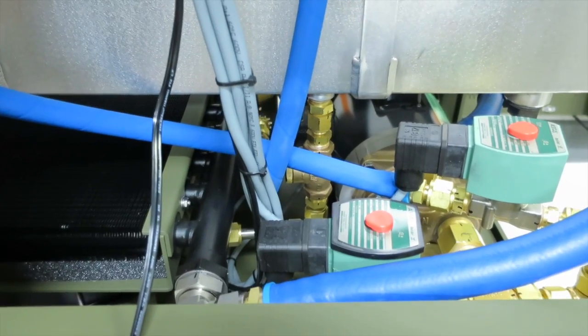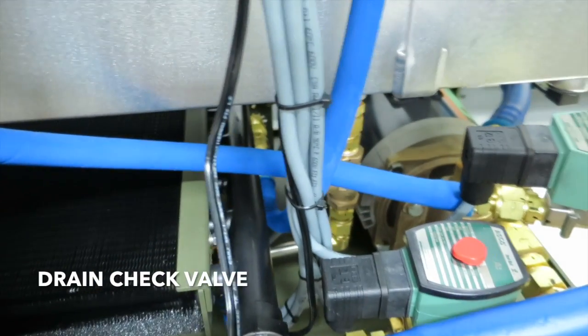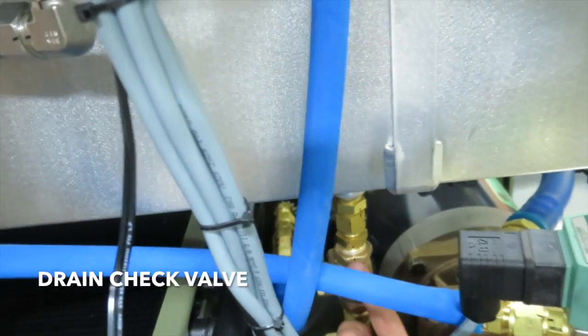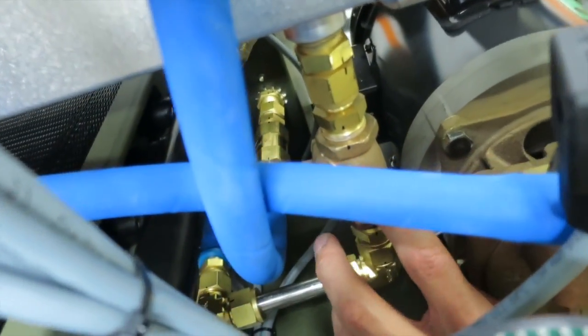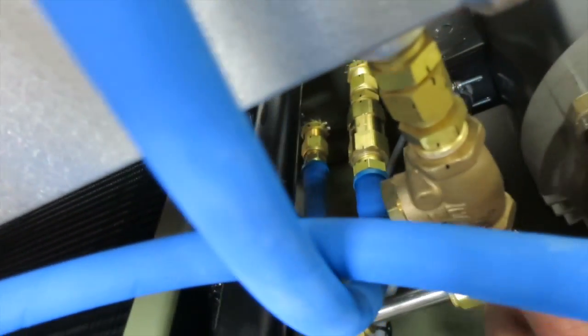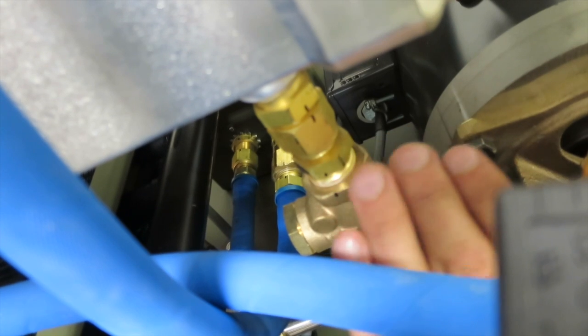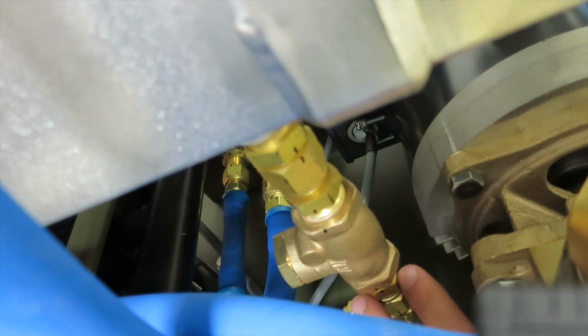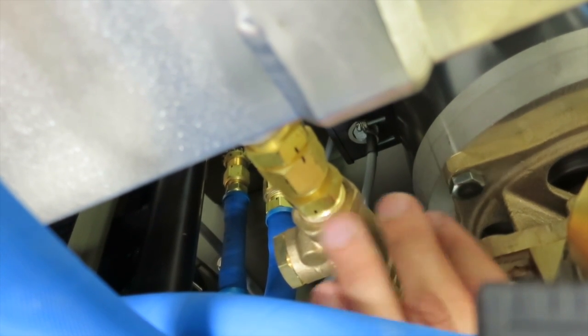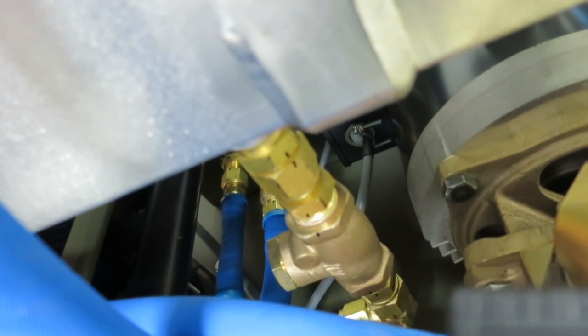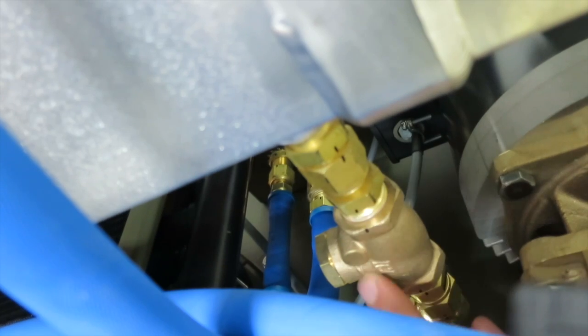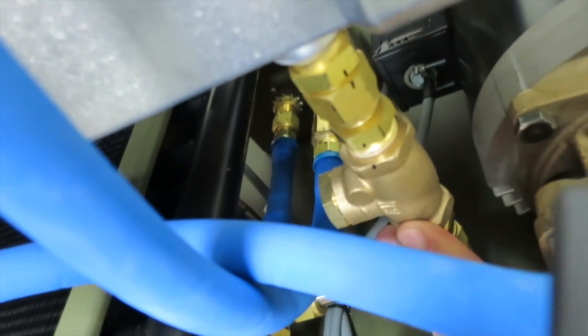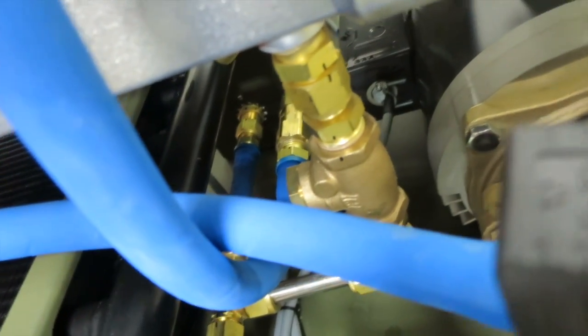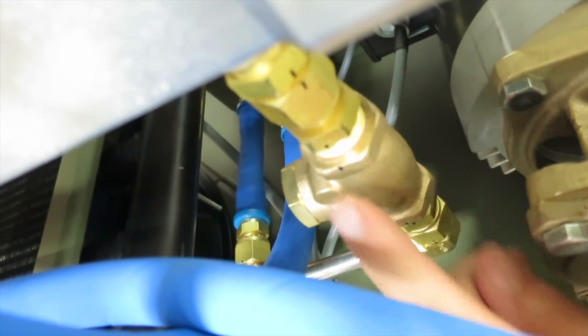Next up is the drain check valve down here. This is a swing check valve, and it's mounted vertically to allow this tank to drain more easily. When you drain this tank, the gate is swung open to allow water to flow out very easily. Now when the water recovery system is on and the pump is running, it closes that gate and keeps water from pumping back up into the tank. So that is the drain check valve. It's a brass valve, and to replace it, again, it's just going to be 2 Swagelok fittings, one on the bottom and one on the top.